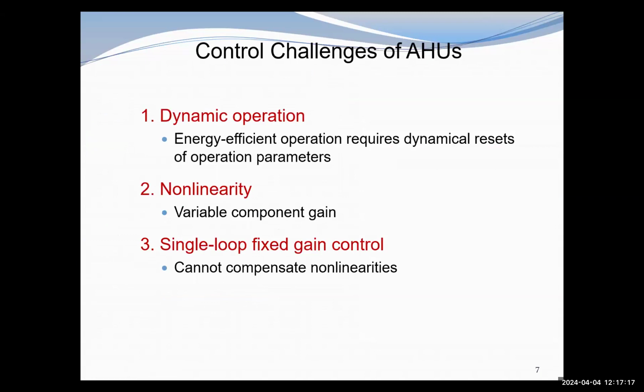The control challenges of the control systems in air handling units lie in three key points. The first is that the systems are operated under dynamic conditions for energy efficient operation. Another is that the components are nonlinear. They have variable gains under these dynamic operation conditions. The third is that the conventional single loop fixed gain control cannot compensate for these nonlinearities. As a result, the system will become more aggressive or unstable.